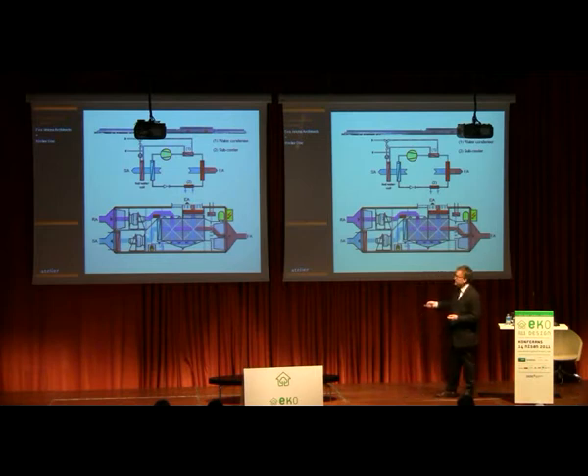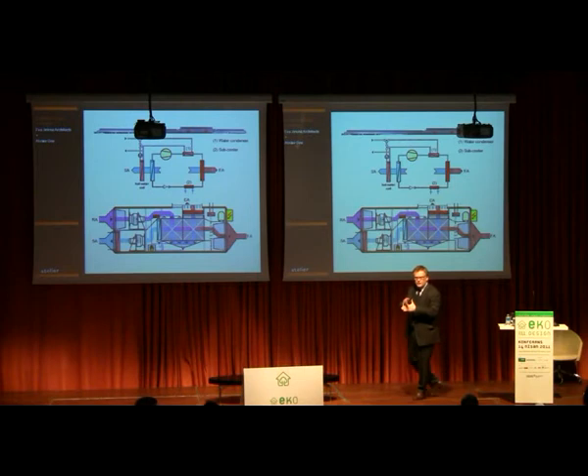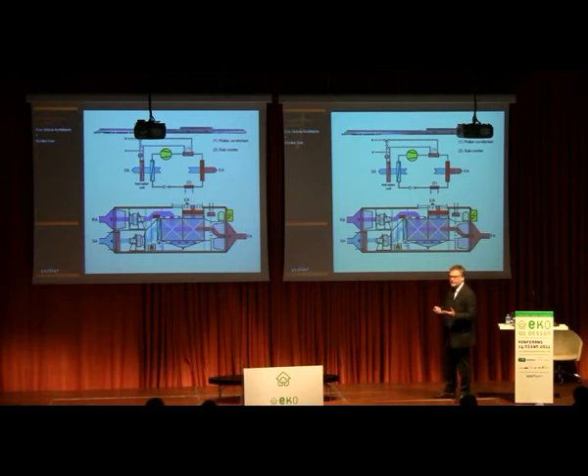In summertime, we can add some evaporative cooling. We spray water onto the return air path - much like the old termite mounds again, sorry to keep mentioning them - which cools the return air down, so the fresh air coming in from outside is cooled as it passes over the other side of the plates. This is called indirect evaporative cooling, or adiabatic cooling, and it's a very powerful tool for providing free cooling.